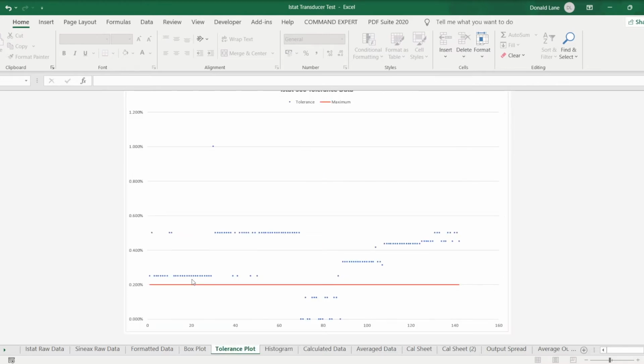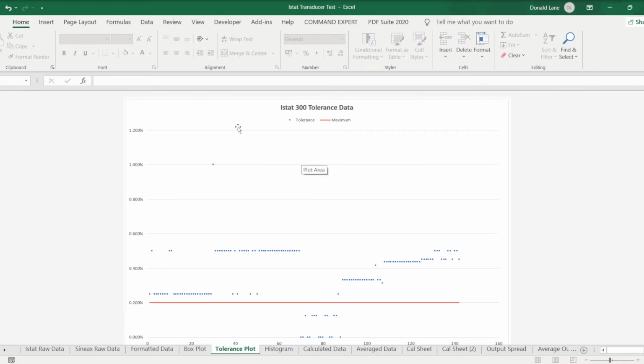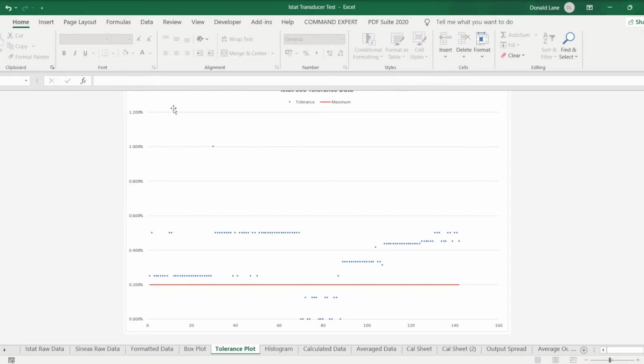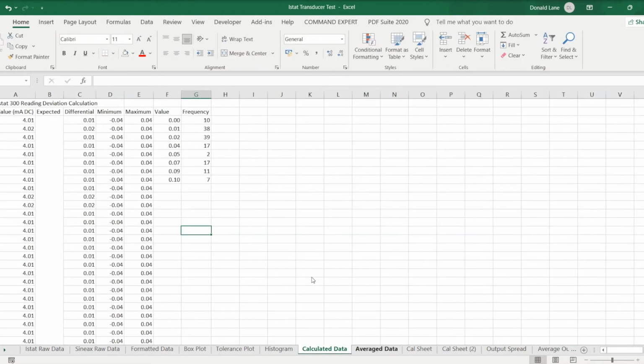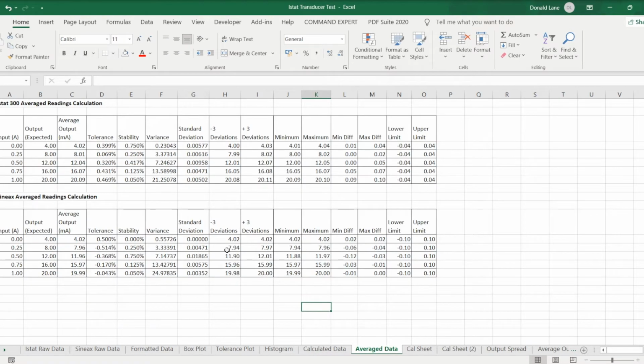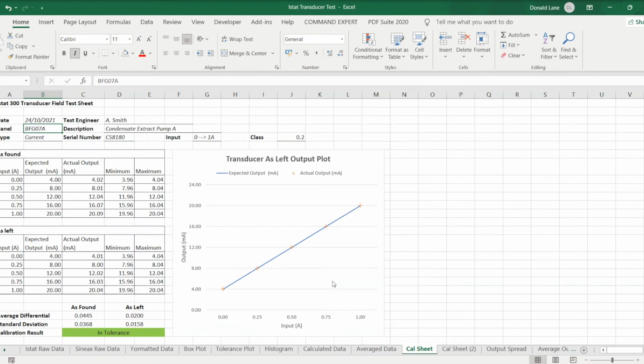If I plot all those tolerances, you can see here, yeah, here we are, this reading here. This is the 1% reading, so you see it's somewhere around about reading number 30 in there. So what I would actually do is remove any reading that looks erroneous like that. Could occur for any number of reasons really, but it doesn't fit in with the rest of the data. So that would get taken out as well, and from that I then end up with a complete table where I've calculated the differential values, and I can then move on to average data, which eventually leads me on to the calibration sheet. And I would actually PDF this up and give this to the client. There you go.